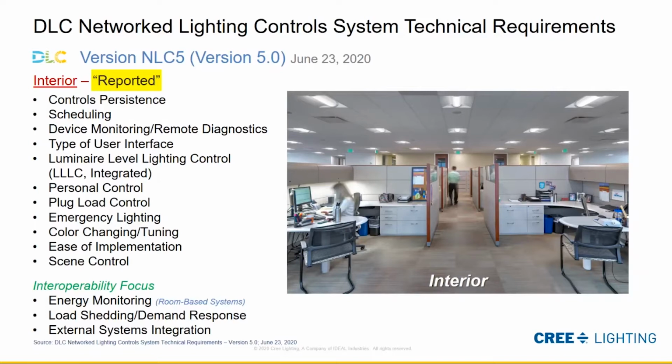Whatever the last settings for daylight, occupancy, and so forth were given to that luminaire or group still function. So if the controller's lost or the Wi-Fi goes down, the system itself continues to work as it was last requested to work. So that's important because obviously that does happen.